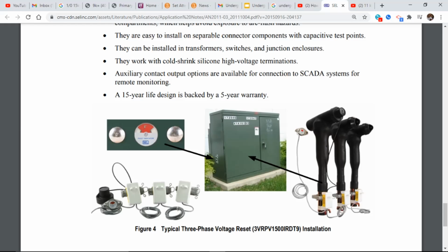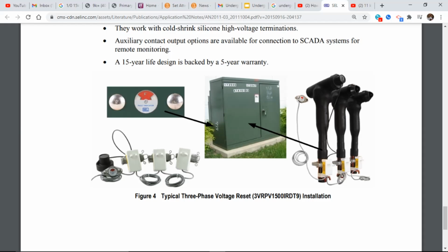What you're seeing here is three elbows going into a transformer right here. They have a device that you can strap around the primary conductor. You see it down here in the lower right-hand side. I'm taking my mouse around it. That goes to a cable that mounts on the outside of the transformer, and they put theirs on the side. We typically put ours right down here in front so you could drive by and see it. So if you have a fault on the cable, what is the reading?